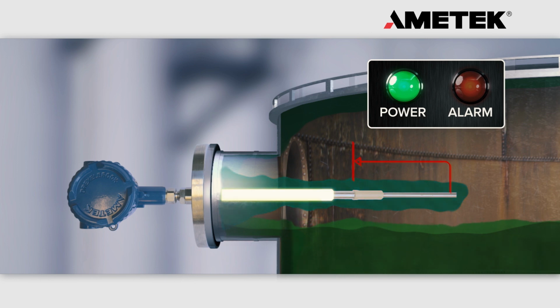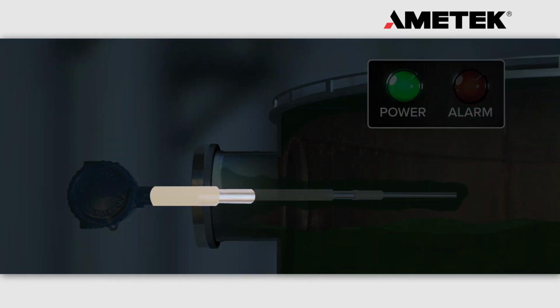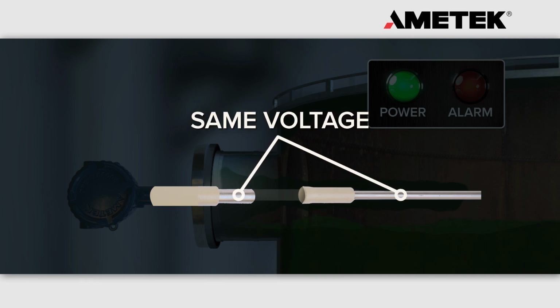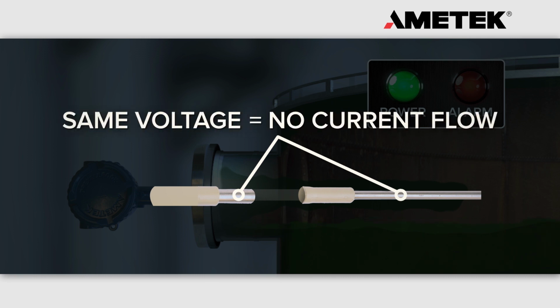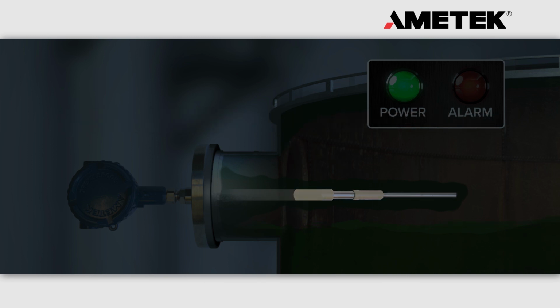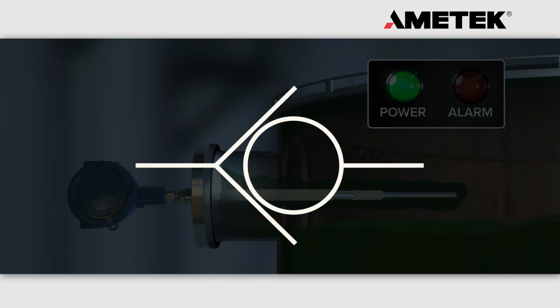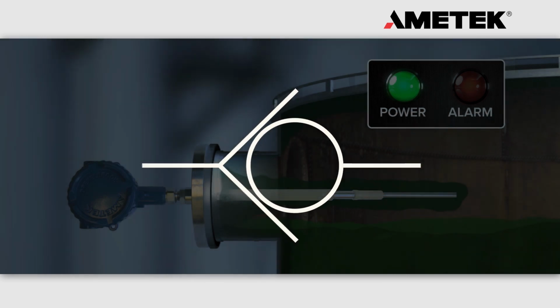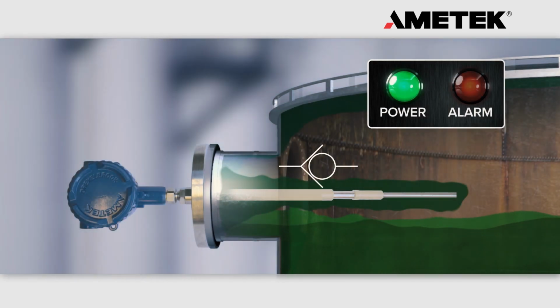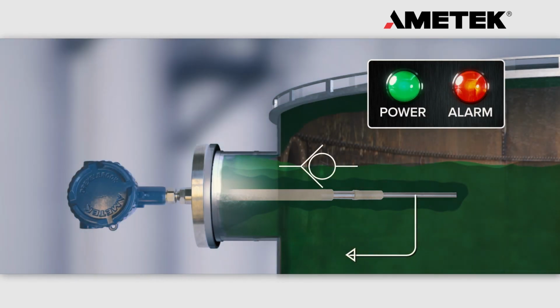How is this done? The Cote-Shield and active rod segments of the probe are at the same voltage potential. When 2 points are at the same voltage, there is no current flow. We've essentially created an electrical check valve. This stops current flow from the active rod through the coating, leaving only one alternative: through the process fluid.